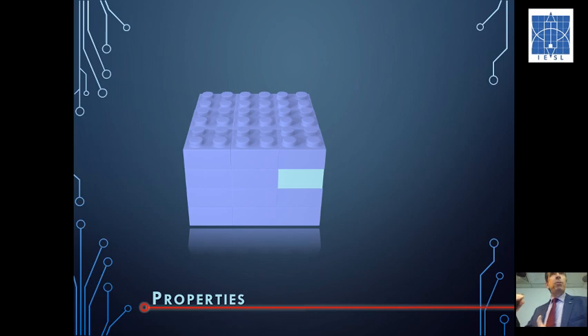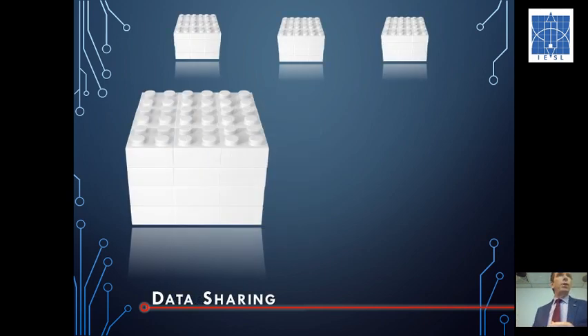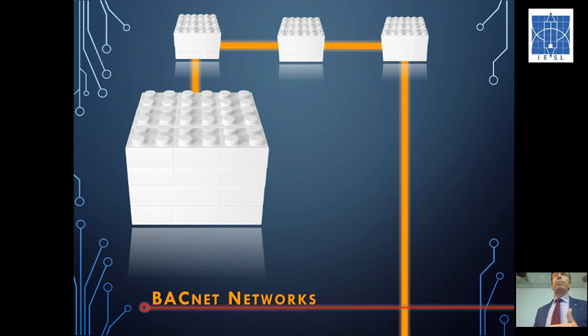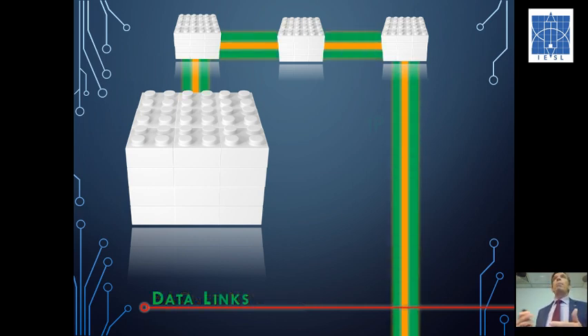So, just to refresh your crash course in BACnet from the ground up: a property defines an object. An object lives inside a host controller, and a host controller resides on a network. The primary purpose of that host controller is to get that piece of information, that object, out to another device or multiple devices on that network. The way that we do that is typically through physical links, which are the different types of data links that we have. The BACnet standard has typically four different types of links. IP, to get information out onto the internet. Ethernet, which is a fast, short network. MSTP, which is a longer range, more cost-effective network. And point-to-point, which is typically just between two devices.